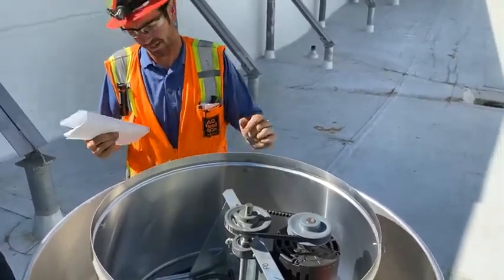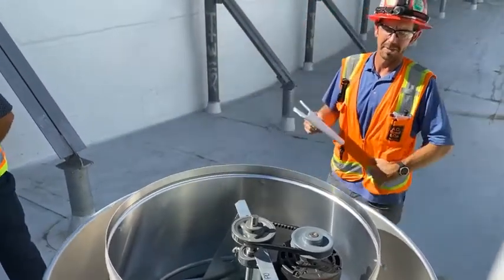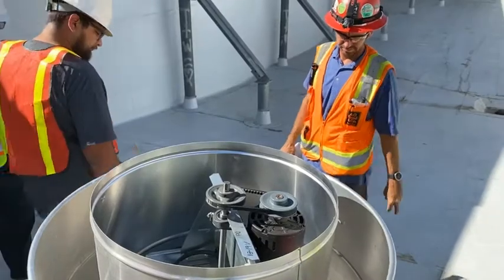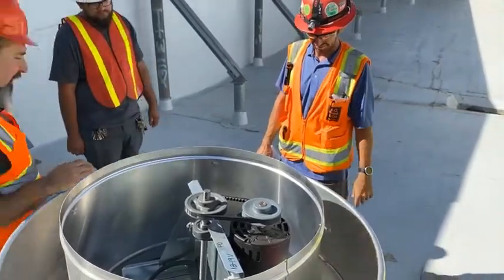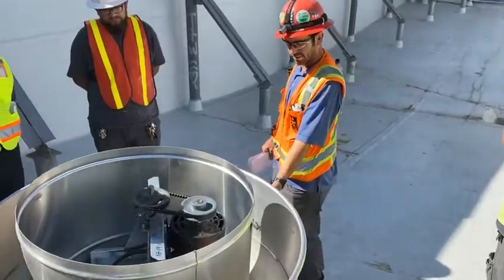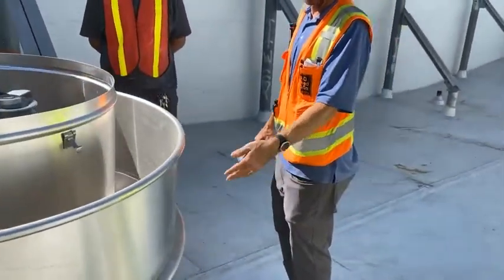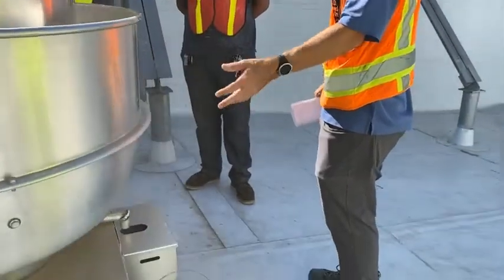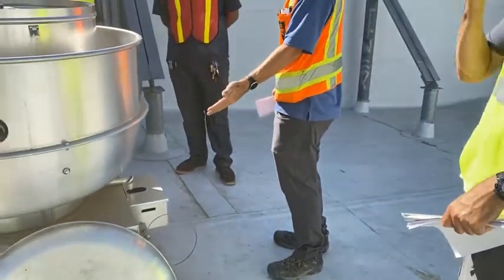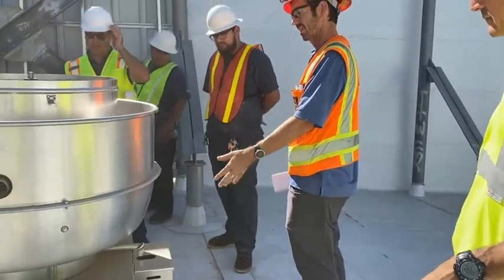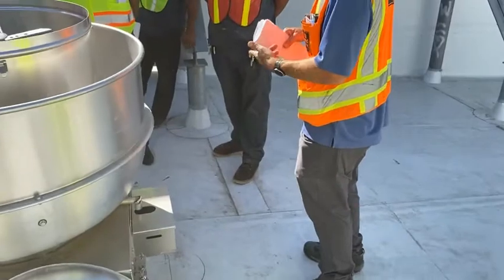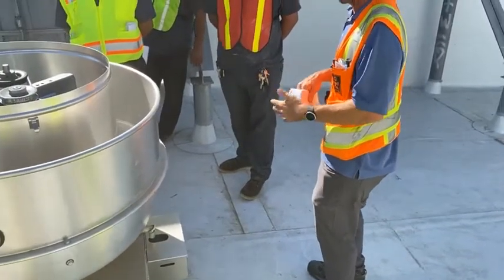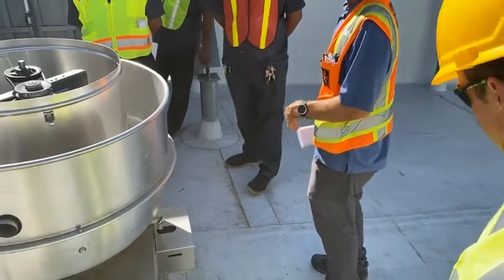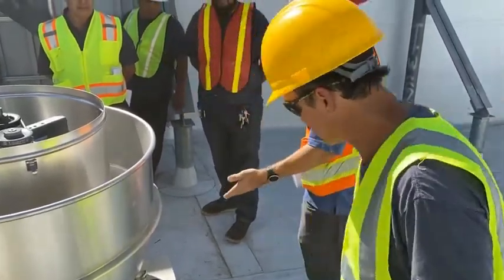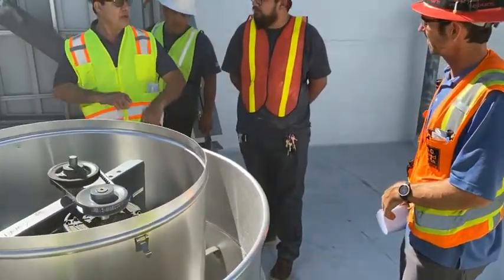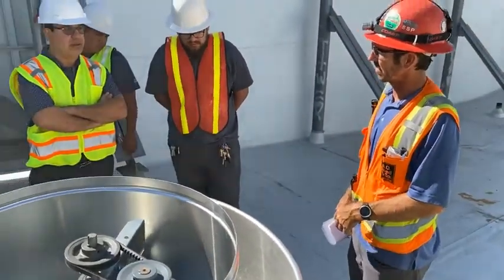Typical mushroom blast fan. This is a grease accepting fan, so there's a grease box over here we need to inspect too. Okay, just watch the levels in there. It's acceptable for it to collect a little bit of water too, so we just have to inspect that. I would say monthly, make sure it doesn't need to be cleaned out, and we'll want to follow the proper procedures in the O&M, or the operation and maintenance manual that deals with cleaning grease. I would assume that's a third party as well, right? Or do you guys clean these out? Okay. So the same thing then.